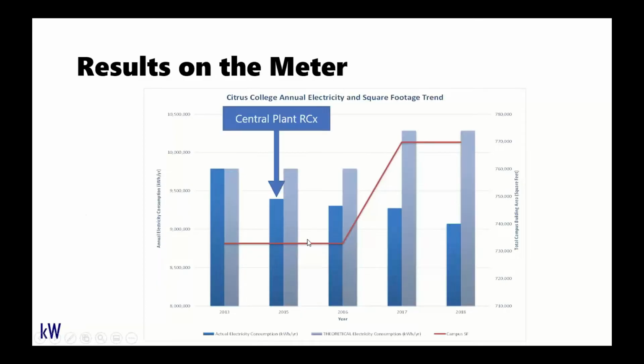And we can see the different projects that were executed here. So this was the first phase, our central plant retro commissioning, which dropped the energy intensity of the campus immediately in 2015. We did our phase 2 retro commissioning after that, right in line with when the building was added, and then phase 3 in 2018. So we had a consistent and regular downward trend in energy consumption, even though the campus square footage increased.